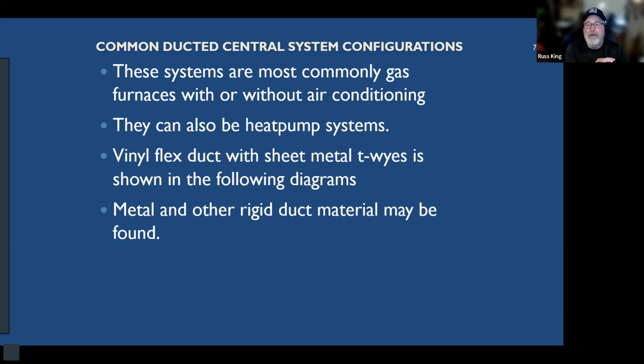Okay. In some parts of the country, they absolutely never use flex duct, and it's very interesting to me that they will only use sheet metal ducts in certain parts of the country. We're out here in California, 99.99999% of all new construction homes use flex duct, and we have been for many, many, many years. And flex duct works great. If it's designed correctly and if it's installed correctly, I would actually prefer flex duct. If I was building my own house from scratch, I would absolutely put flex ducts in my house and not sheet metal ducts. Okay, there's a lot of reasons for that.